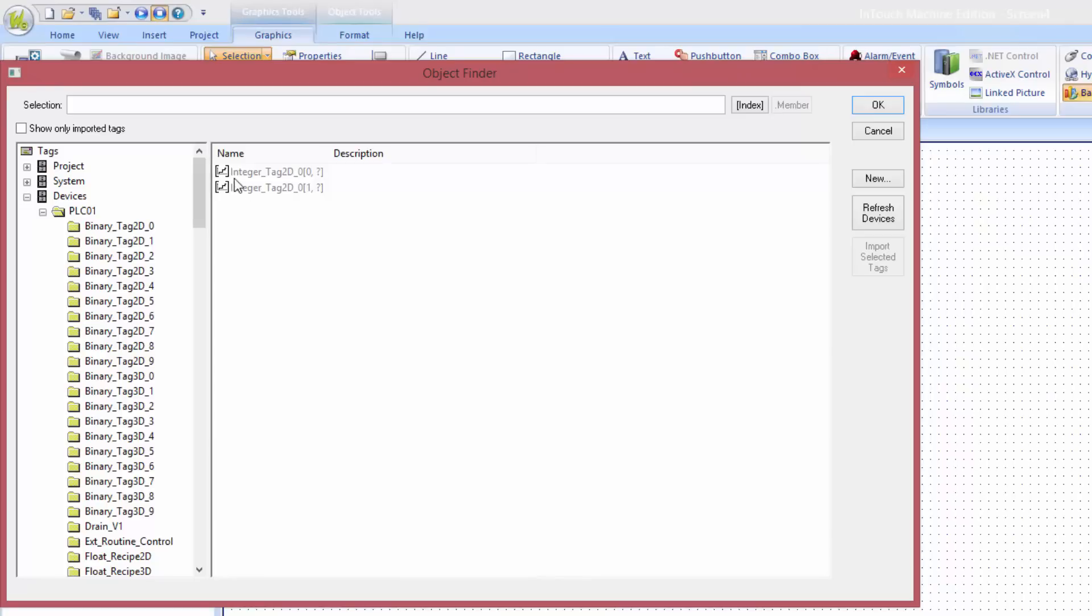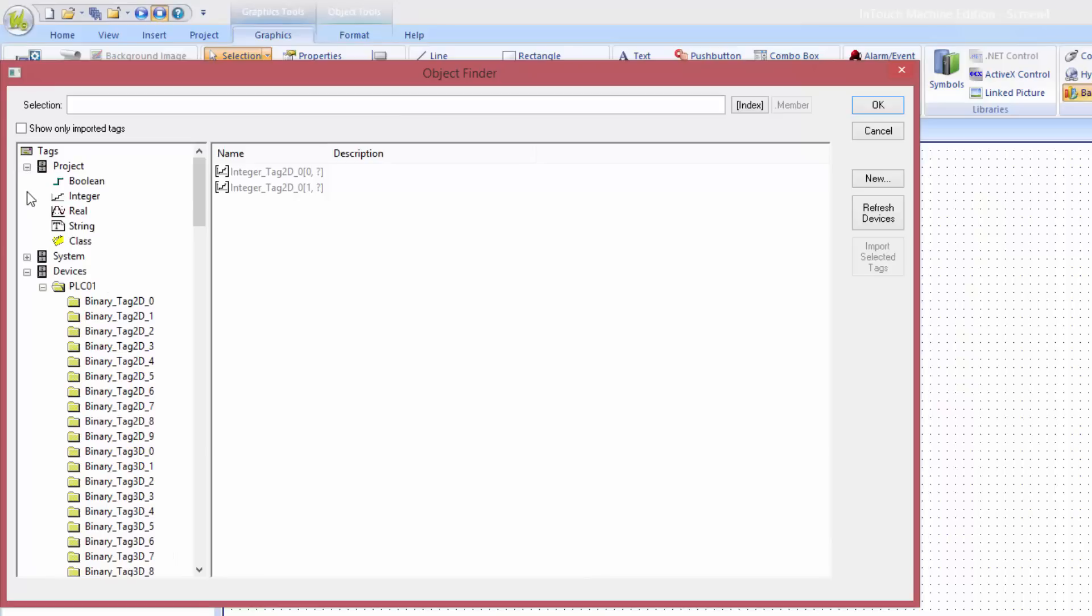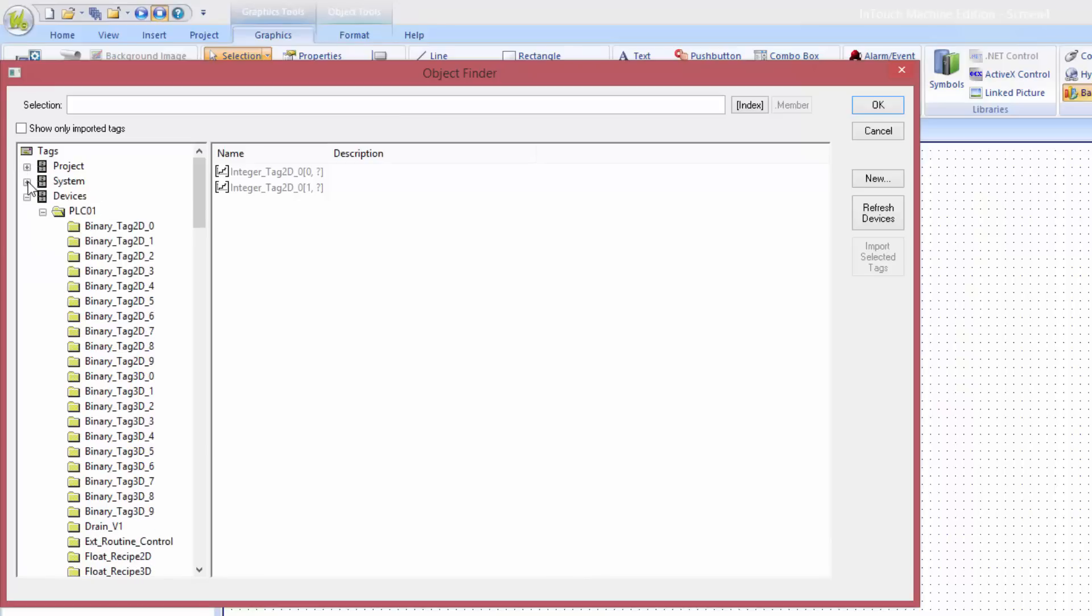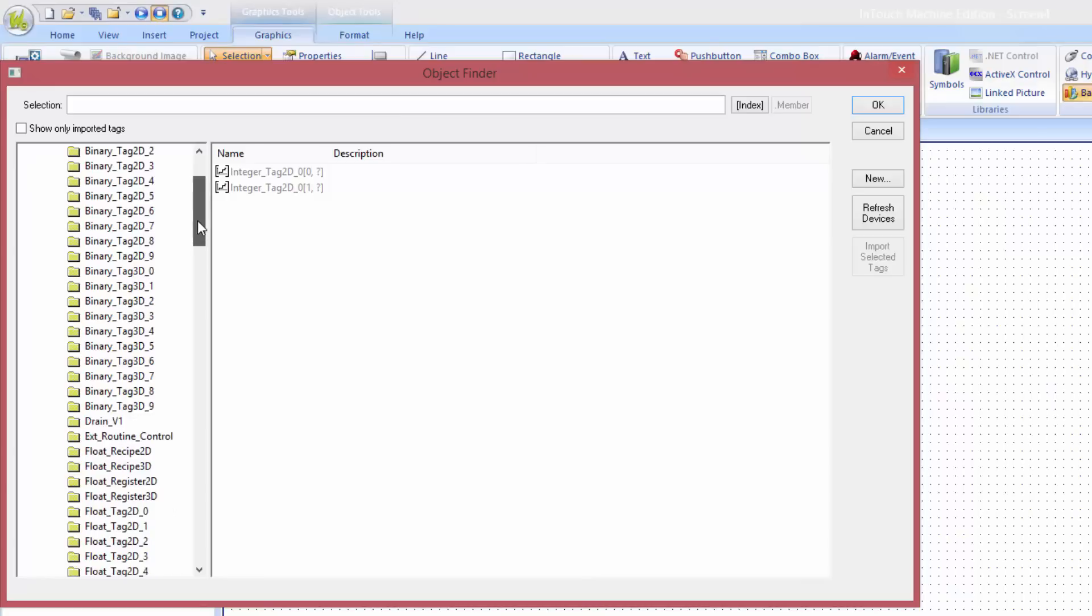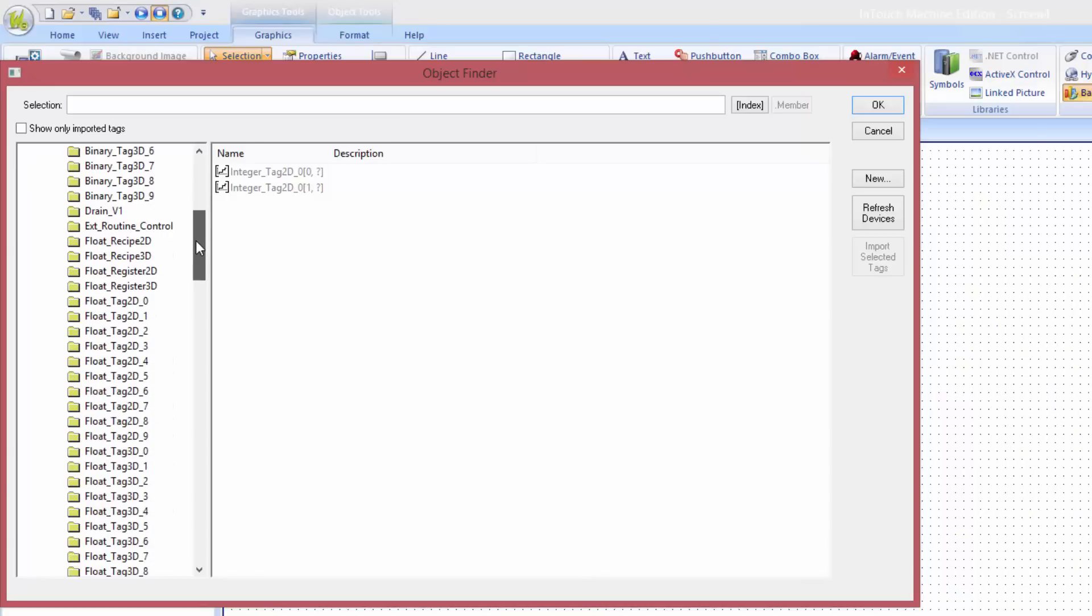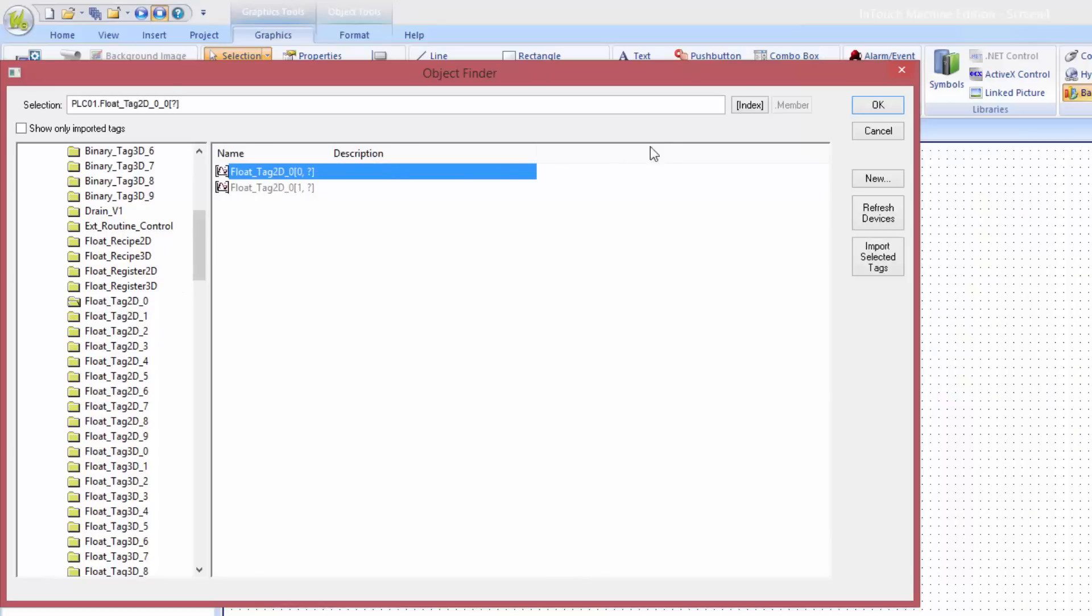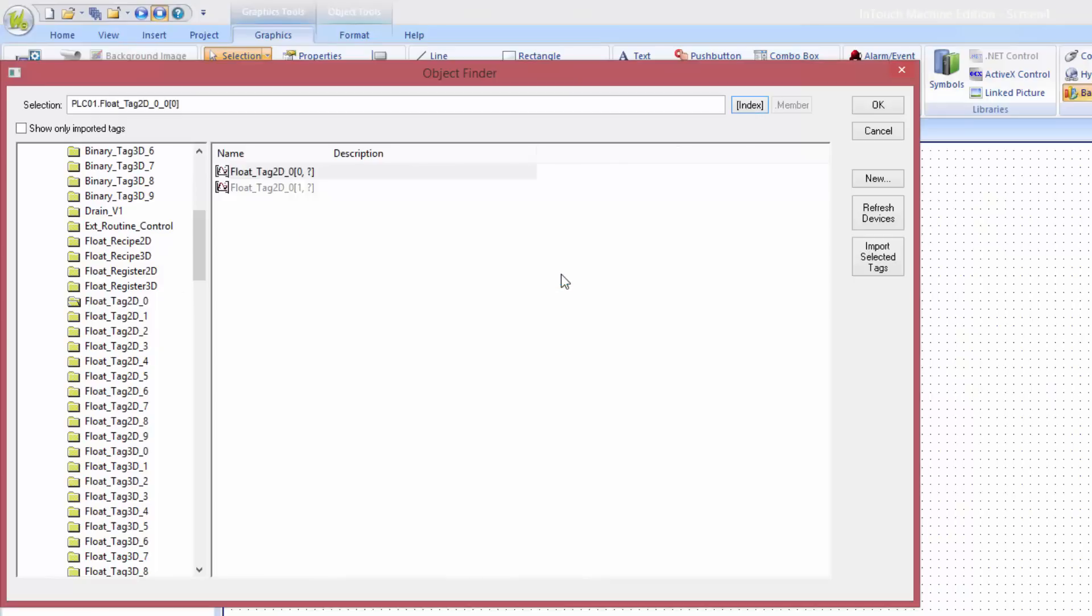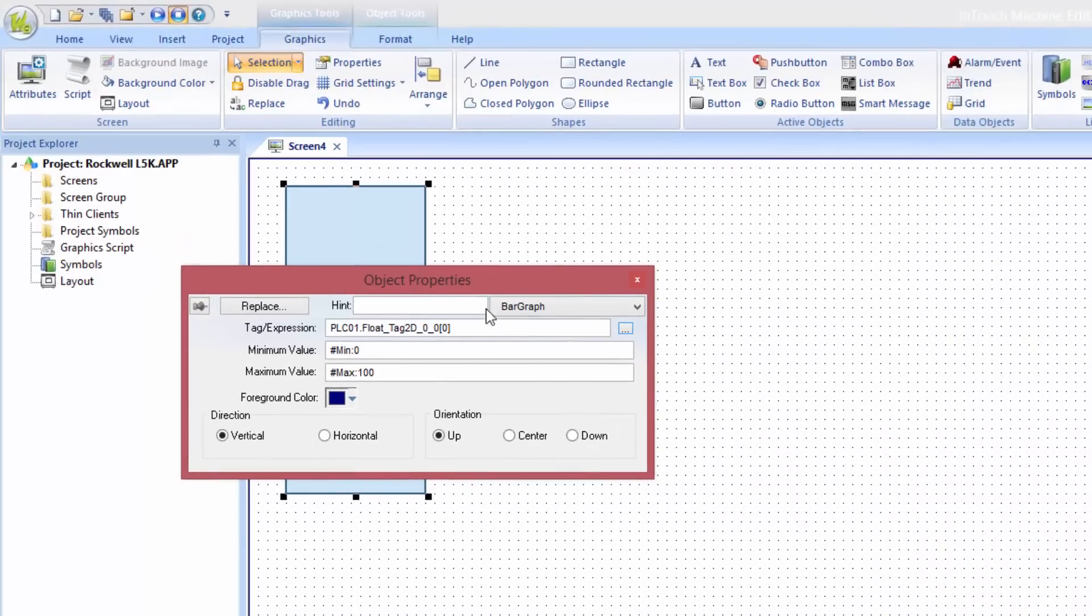The tag browser will show all the tags in the solution. We have project tags that are specific for this project, system tags that are pre-configured, and devices that show the tags that are integrated with PLCs. Here I have PLC01 that are configured as a Rockwell ControlLogix. This PLC is using a lot of arrays. For this animation I want to use float register 2d array 0. I want to use the first index member of the array. Click OK.